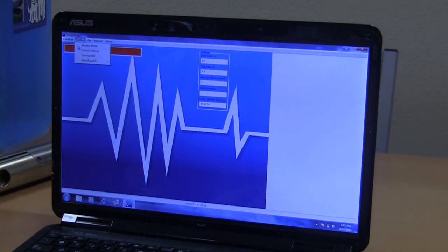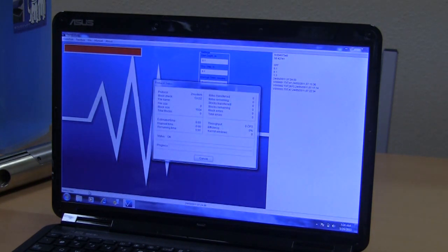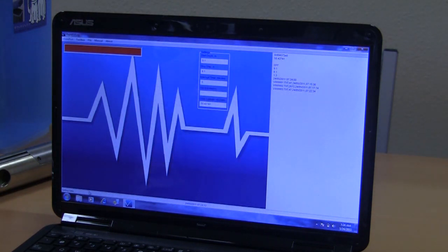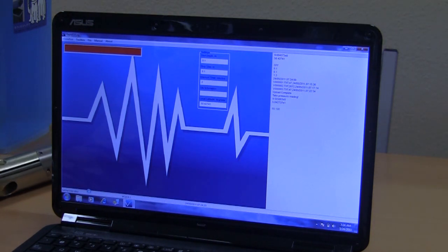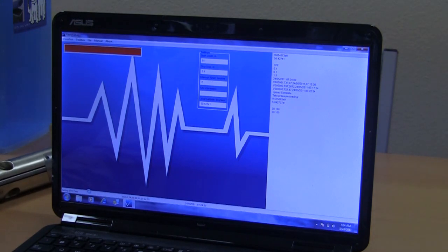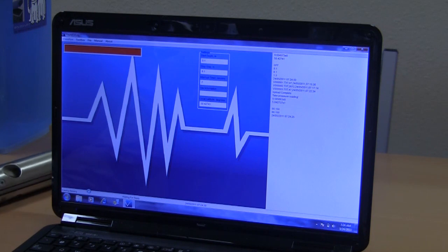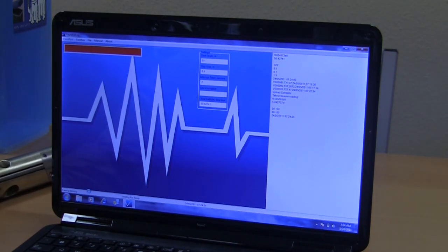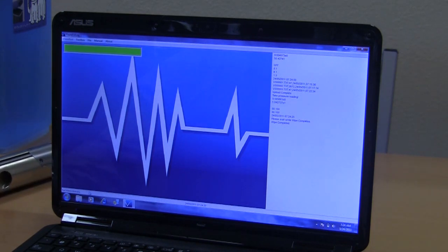So click on monitor mode, this will start the probe running. You can see here it's getting the information from the probe. Any data that may be already on the probe is downloaded and the probe is wiped. It takes a pressure reading in air, so make sure when you're doing this the probe is not partially submerged or being affected by any splashing of water onto the pressure transducer. The memory's been erased, instrument running, green bar. So now we're ready to deploy the instrument. We've got 2 minutes to deploy it before that procedure occurs again.